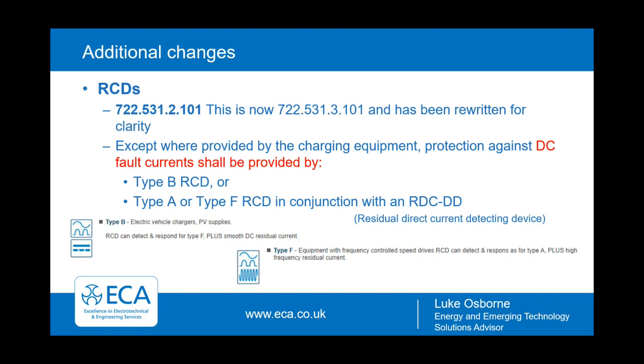Type Fs weren't previously cited in the previous regulations, they are now. They're typically more expensive and rarer than Type Bs, but they're now becoming more available. Type F RCDs, some vehicle manufacturers do specify them, so do check with your clients on the type of vehicle that they're intending to use. And the reason for Type Fs is with more and more DC componentry and frequency controllers being installed in commercial and domestic buildings, Type Fs are required to remove any of the DC fault currents that can be presented. A common thing that is now appearing is a modern day washing machine utilizes a frequency inverter to control a three-phase motor, which then in turn can put noise back on the system.